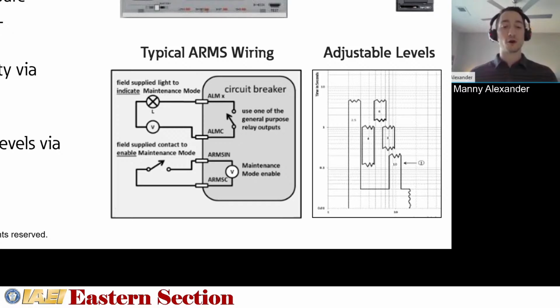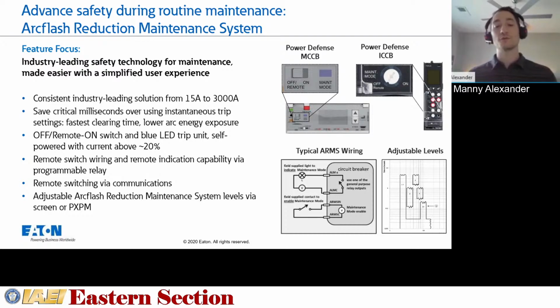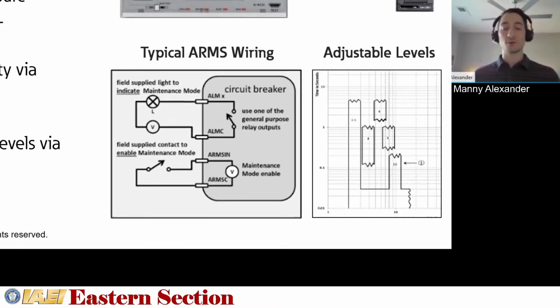In some cases, using ARMS can actually reduce the NFPA 70E hazard risk category classification. So, potentially requiring less PPE to work on an assembly with breakers. And when ARMS is engaged, the breaker is put into maintenance mode. Maintenance mode can be turned on via a local switch at the trip unit, like you see on the screen. It could be done by remote switching via a 24-volt DC powered contact or through the built-in communications. So you can confirm that maintenance mode is on by the solid blue light on the front of the trip unit, by using a relay contact connected to a remote light or other signal, or by reading the status via the communications as well.